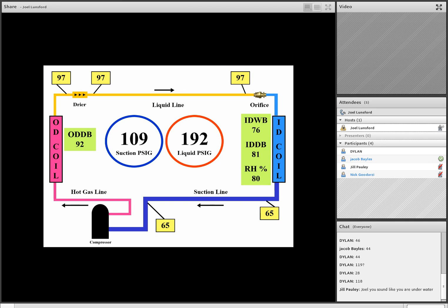So as we take a look at that, we see our wet bulb temperature is 76. So on your superheat chart, find 76 or close to it. I see that there's a 75-degree green block on my indoor return air temperature. So find 75. And we have an outdoor air temperature of 92 degrees. So find that 75-degree wet bulb temperature and then go down and correlate 92-degree outdoor air temperature. And tell me, team, what should my superheat be under those conditions?